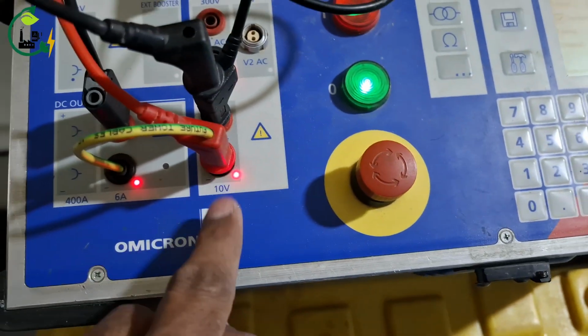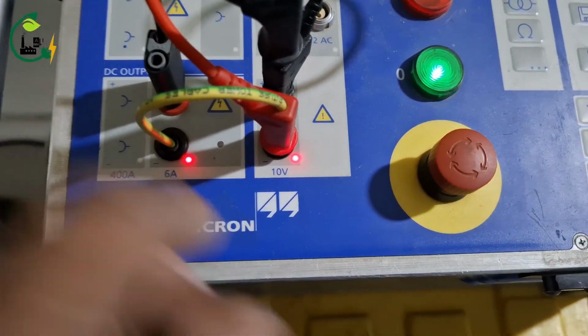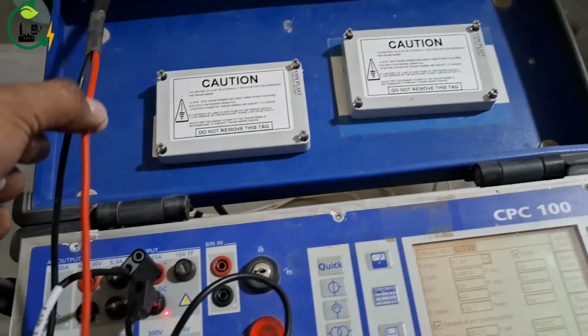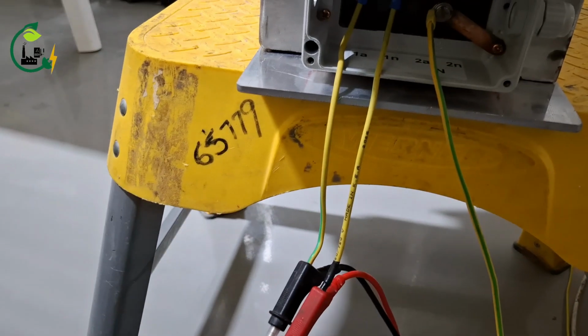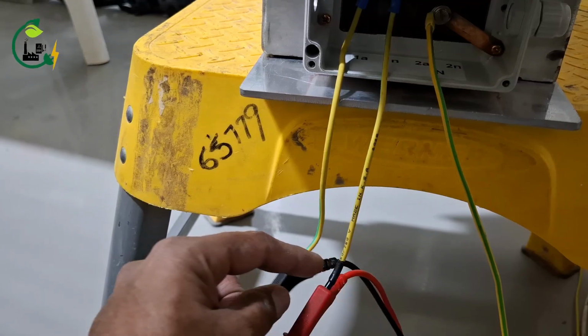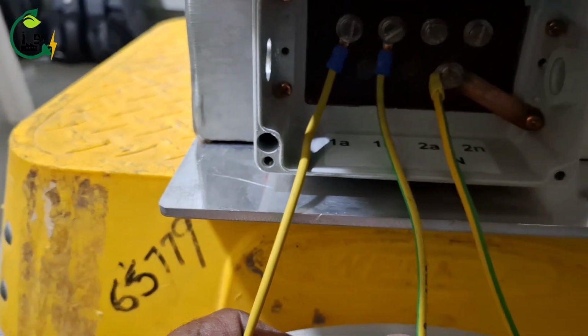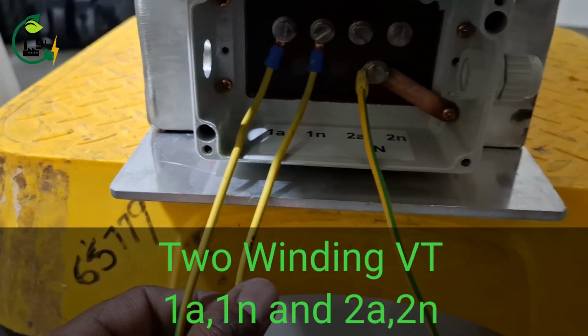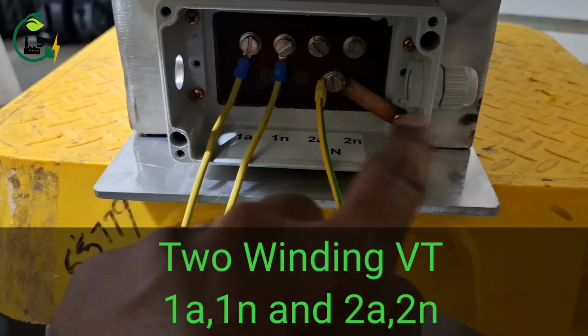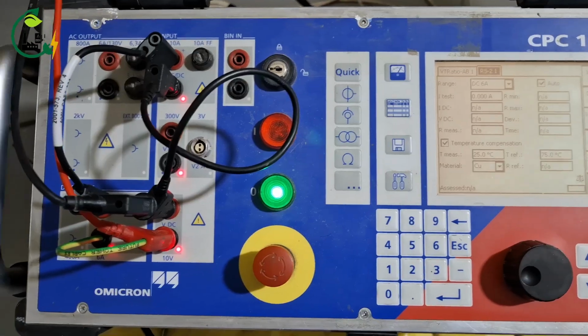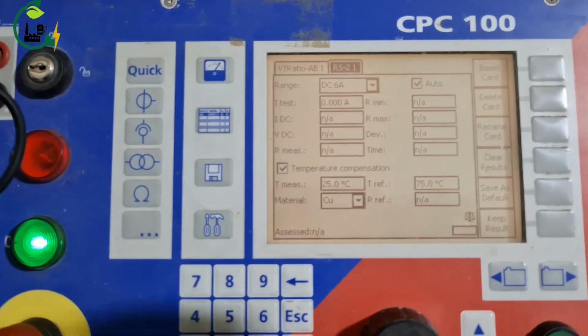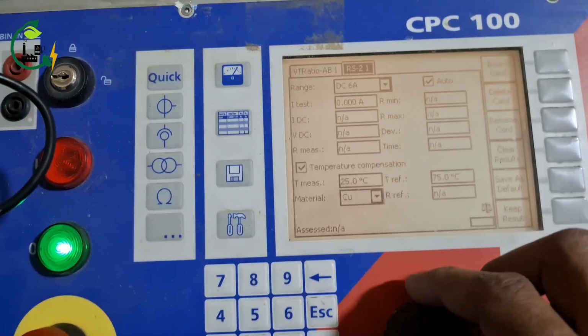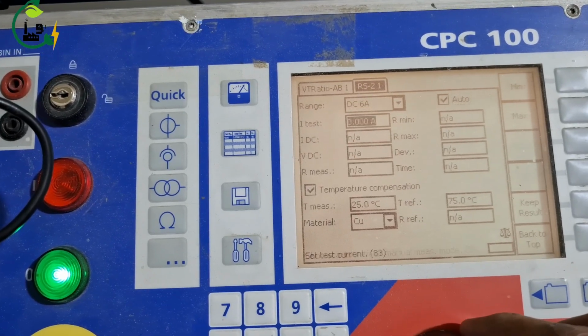Secondary winding resistance. This is the negative, so the 6 ampere negative I connected to the red, and the red I connected here, same to the secondary winding, to check the winding resistance of secondary winding 1, because there are 2 windings, so I connected with winding 1. In this winding resistance test there is no need to connect the primary, we can remove the primary wires.